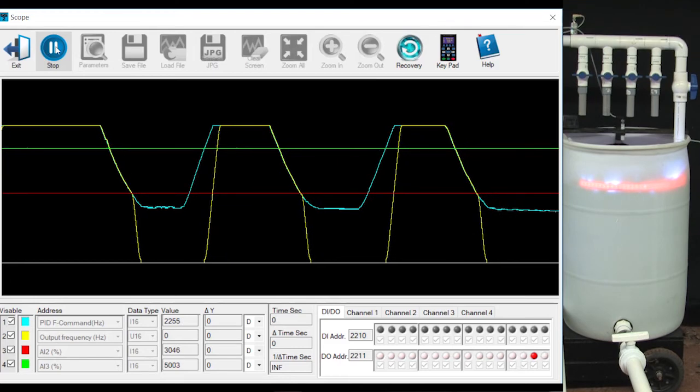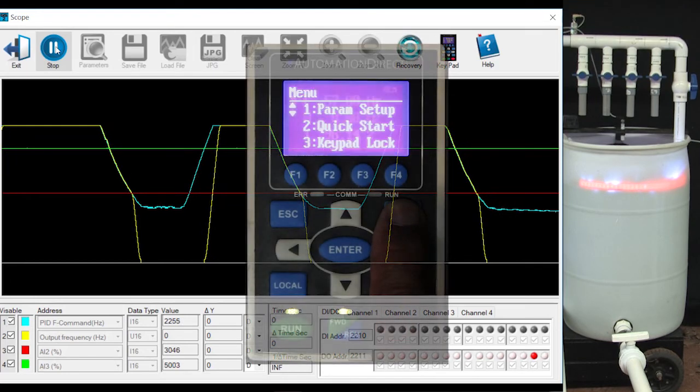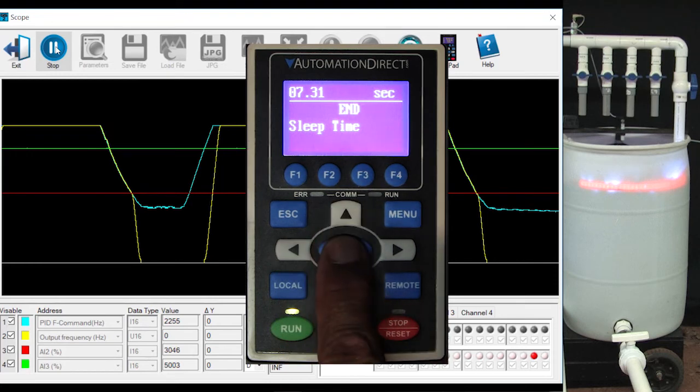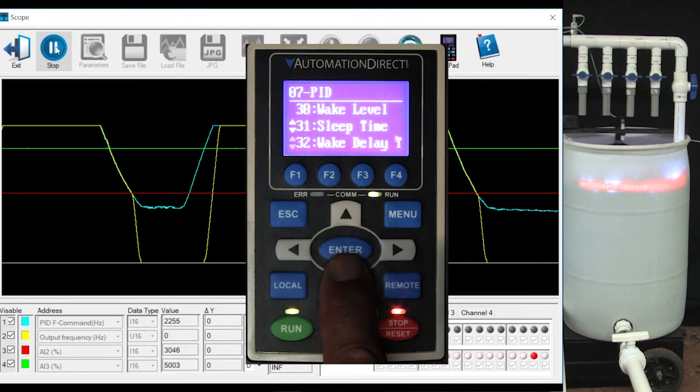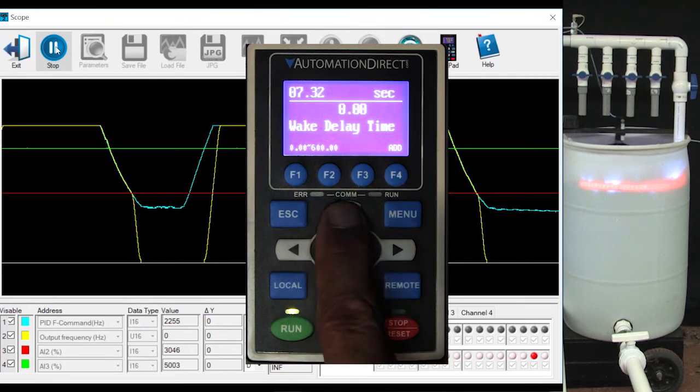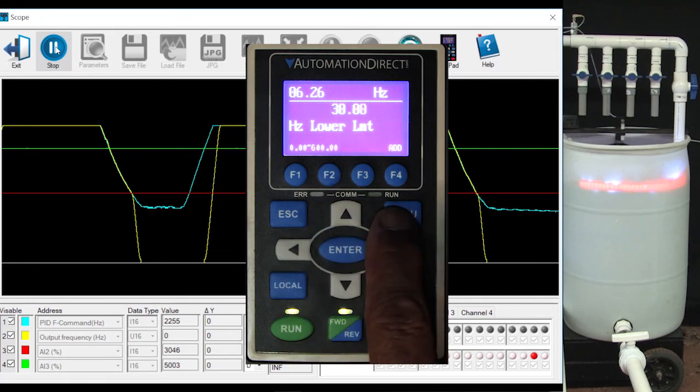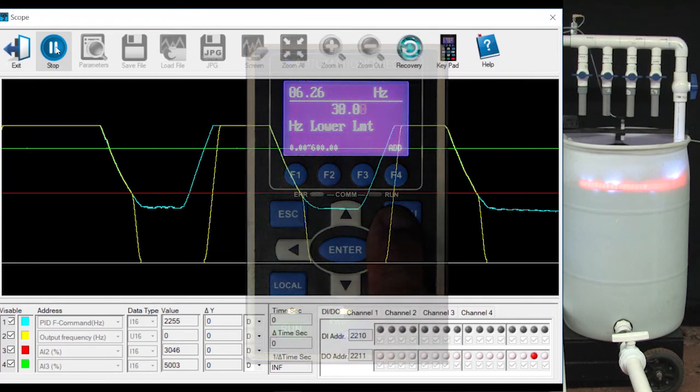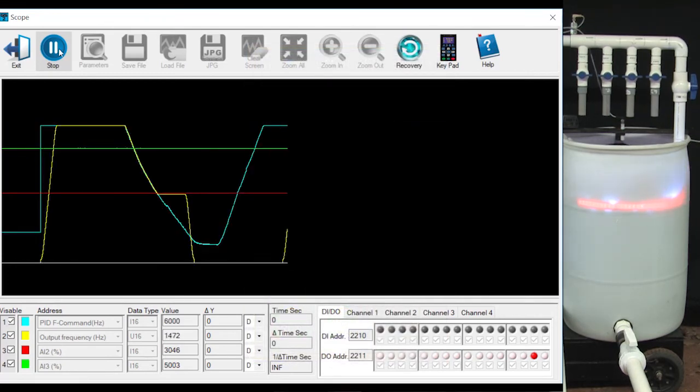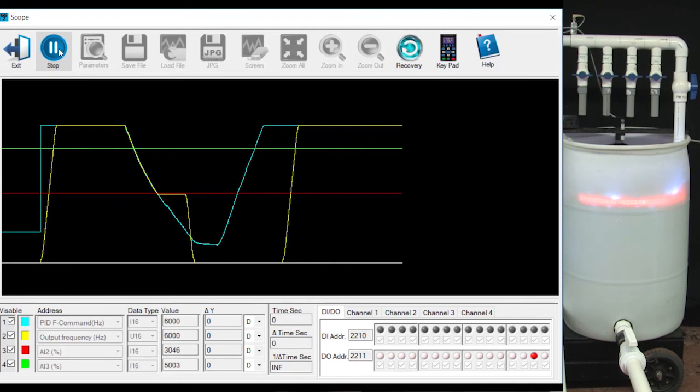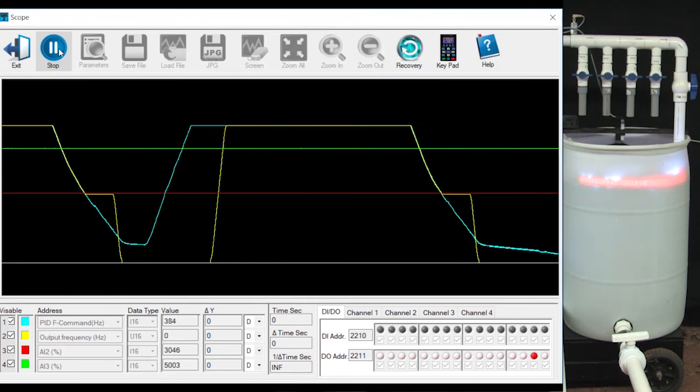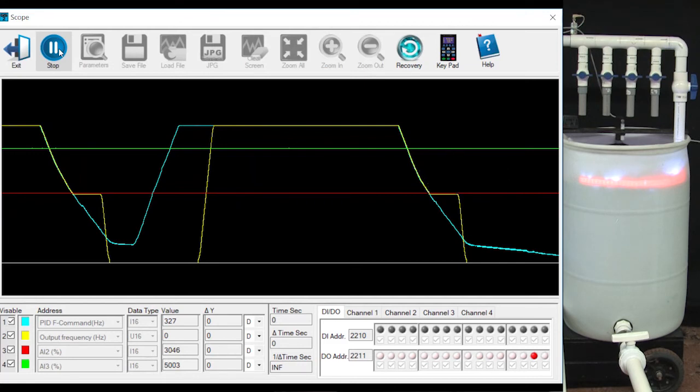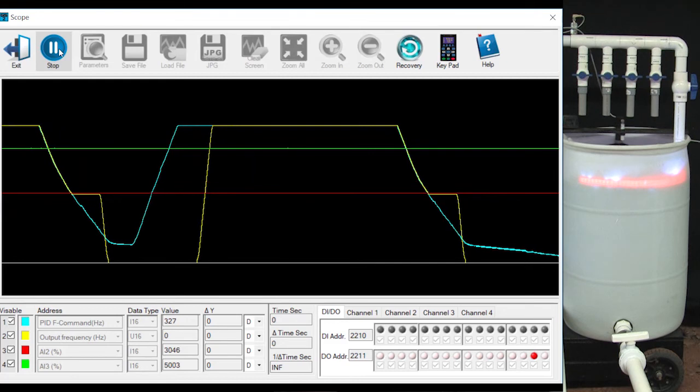You can also delay sleep and wake up. Let's set the sleep delay to 2 seconds and the wake up delay to 2 seconds. I'm also going to set this min drive speed to 30 Hz. You'll see why in a minute. Run the same test and this time sleep mode saw the PID frequency command hit the sleep level, waited 2 seconds and then turned the motor off. So by adding an appropriate sleep delay you can get a little extra water in a tank that you didn't get before because sleep mode was shutting the motor down before we reached our set point.